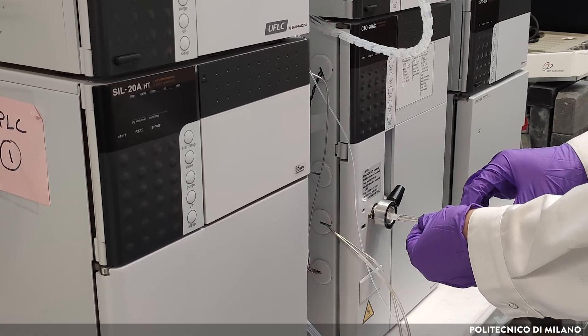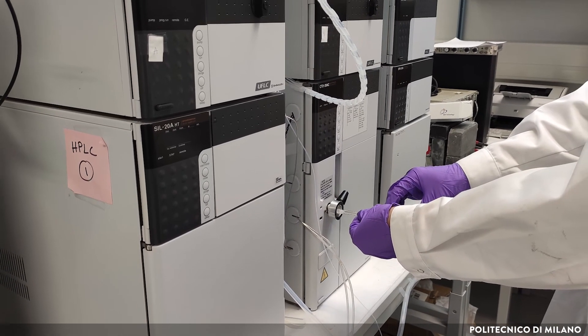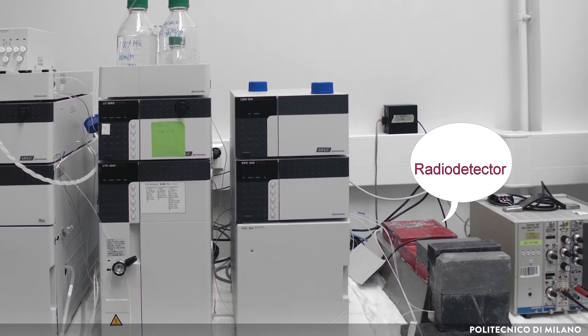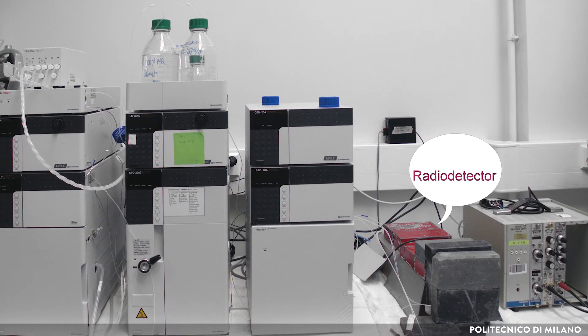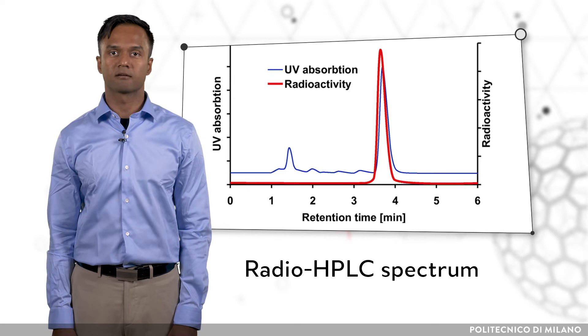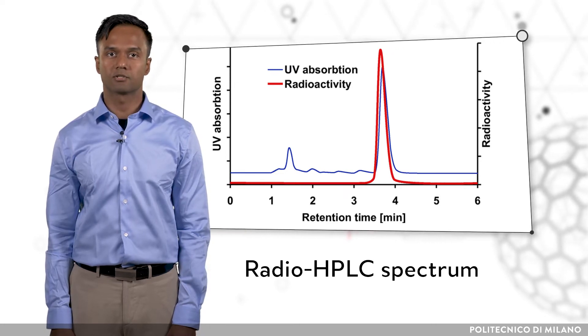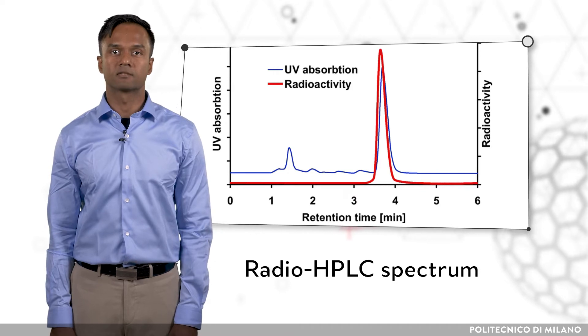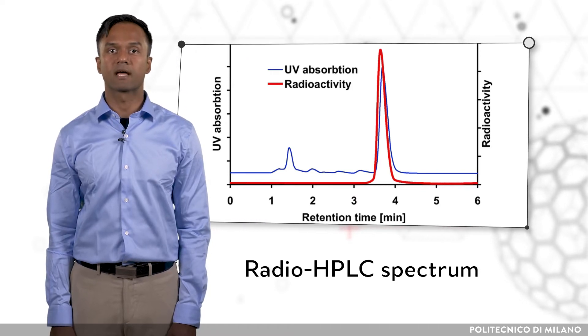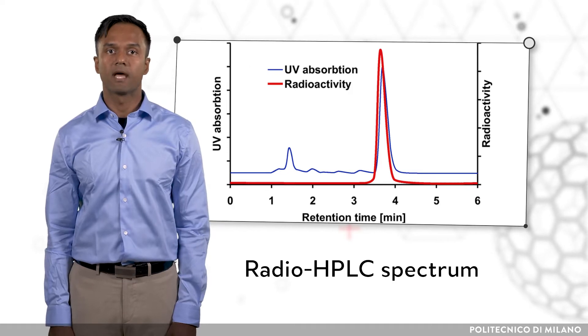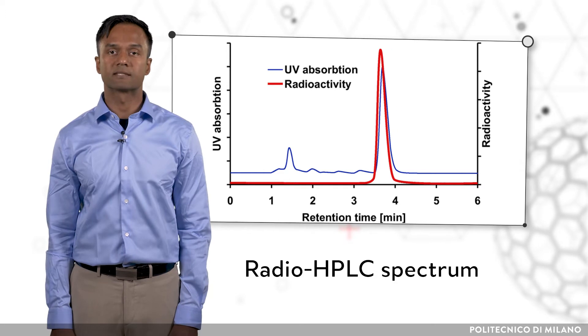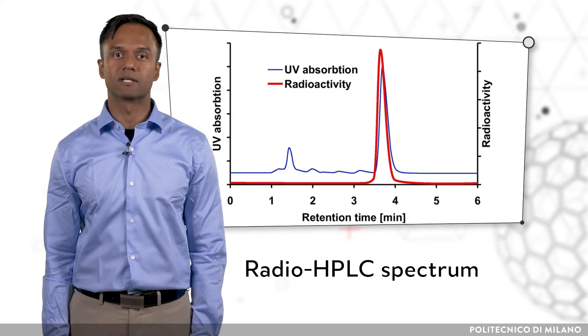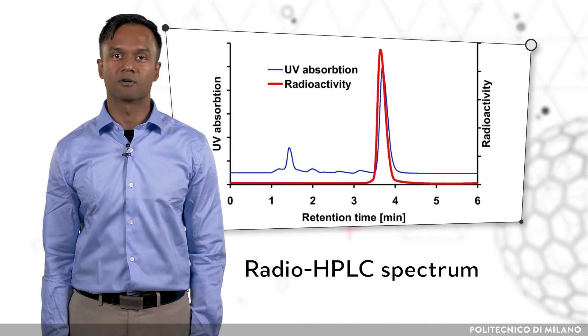RadioHPLC exploits liquid chromatography to separate the different components present in the radiopharmaceutical, and a radiation detector attached downstream works in real-time to identify these components. In an illustrative RadioHPLC chromatogram, the blue line shows the number of organic compounds in the mixture, whereas the red line is obtained from the radiation detector. There is one major radioactive component shown by the single red-lined peak, and one major organic component shown by the single blue-lined peak. Since both peaks coincide, it is possible to assess the incorporation of the radioactive species into the organic molecule.